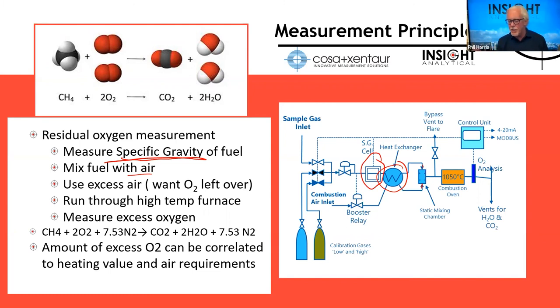So there's a number of ways that this measurement is important. It's most important to the operation of the burner because it allows them to quickly assess the interchangeability of fuels. So if we're at an operating gas plant or refinery, our fuel gas can change composition. Also, we may not always have enough fuel gas, and we may be looking at mixing that in with sales gas or pipeline quality natural gas. As those two mix together, we change the chemical composition of the stream. And if we don't change the airflow rate to the burner in proportion to the changes that are going on, we end up running the burner off its optimum operating ratios. So if there's going to be a lot of variation in the fuel that we're putting into the burner, it's going to require that we make some measurement of how we adjust the air in relation to it.